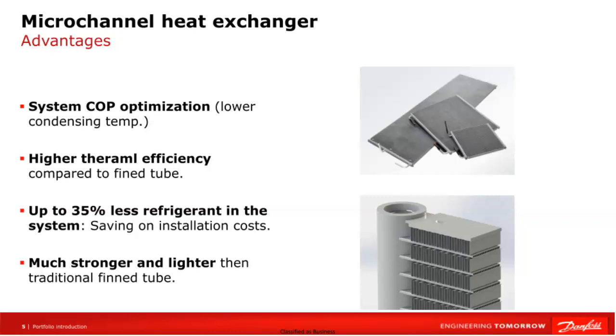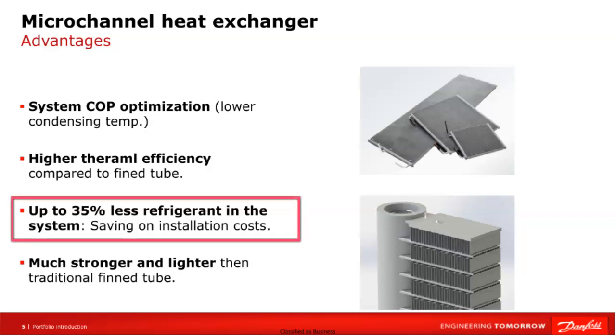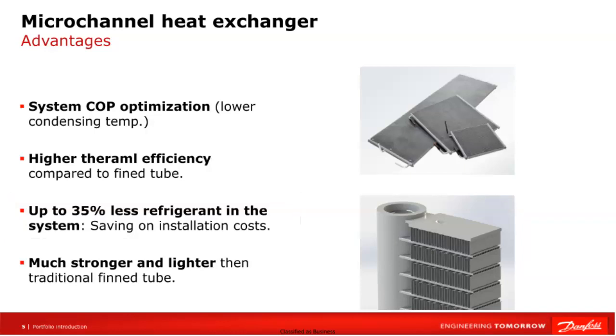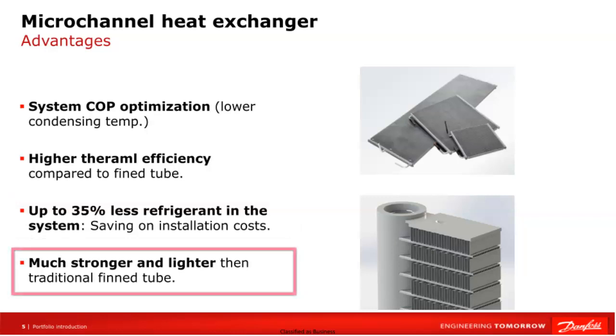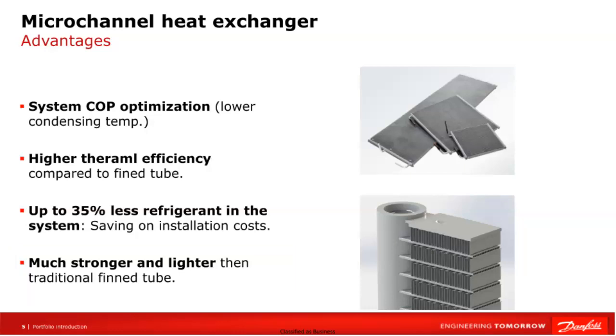Another key aspect is the much smaller internal volume of the microchannel exchanger compared to the fin and tube one. Thanks to this system, with this type of unit can use up to 35% less refrigerant, which is important in the face of rising refrigerant costs on the market. Additionally, the design of microchannel heat exchanger is completely different than traditional finned tube heat exchangers, which makes them much more durable and lighter. This in turn affects the weight of the entire condensing unit.